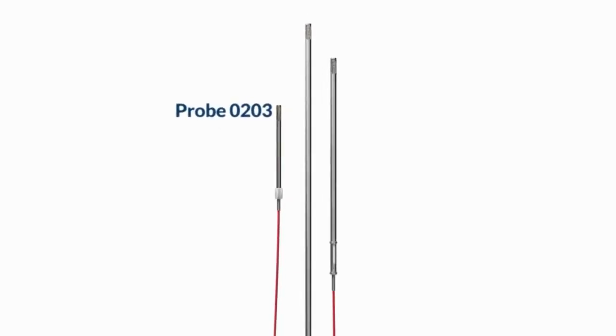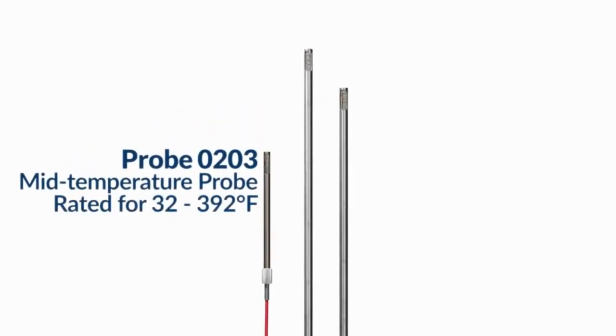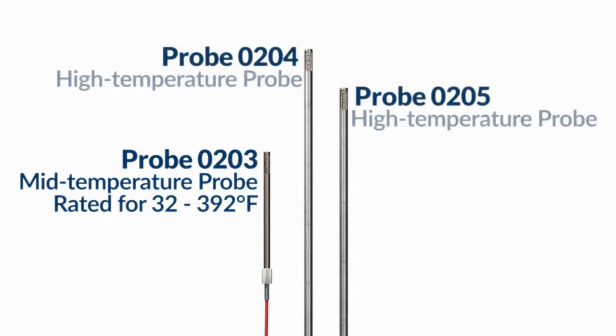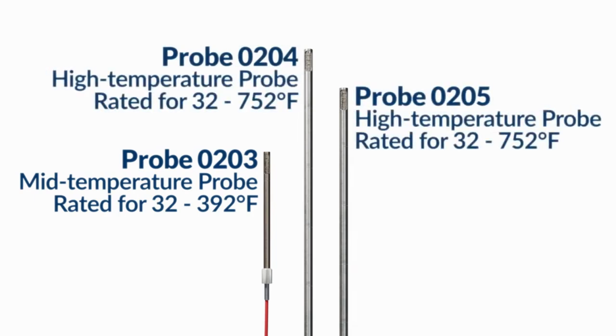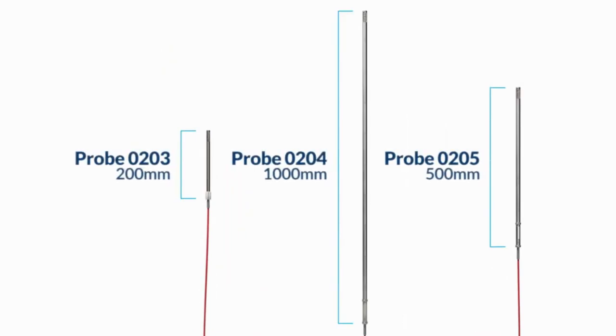When ordering your high temperature anemometer, you'll need to decide which of the 3 probes you'd like to include in your package. Probe Model 0203 is our mid-temperature probe, rated for temperatures between 32 and 392 degrees Fahrenheit. Probe Model 0204 and 0205 are high-temperature probes that measure airflow between 32 and 752 degrees Fahrenheit. However, the 0204 probe is 1,000 millimeters long compared to the 0205 probe, which is 500 millimeters long.